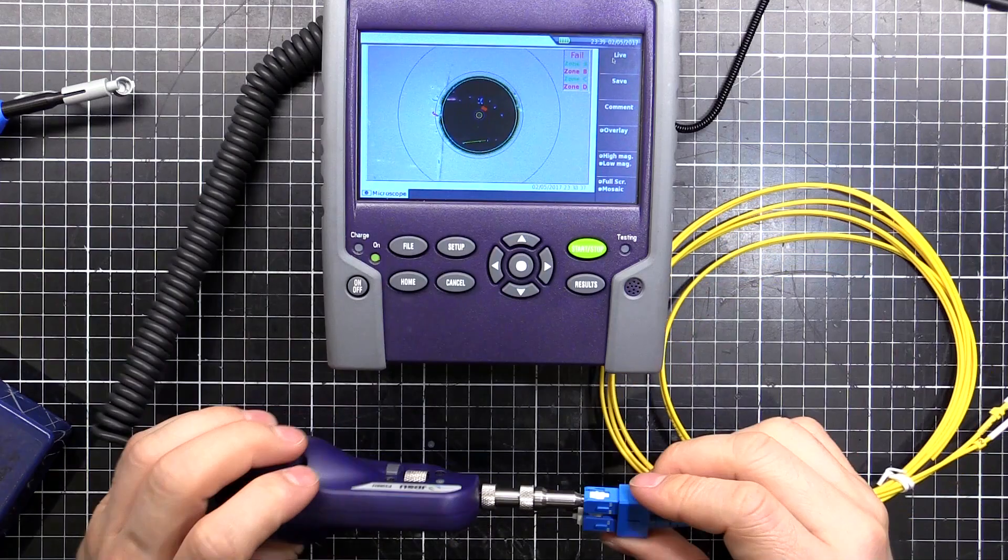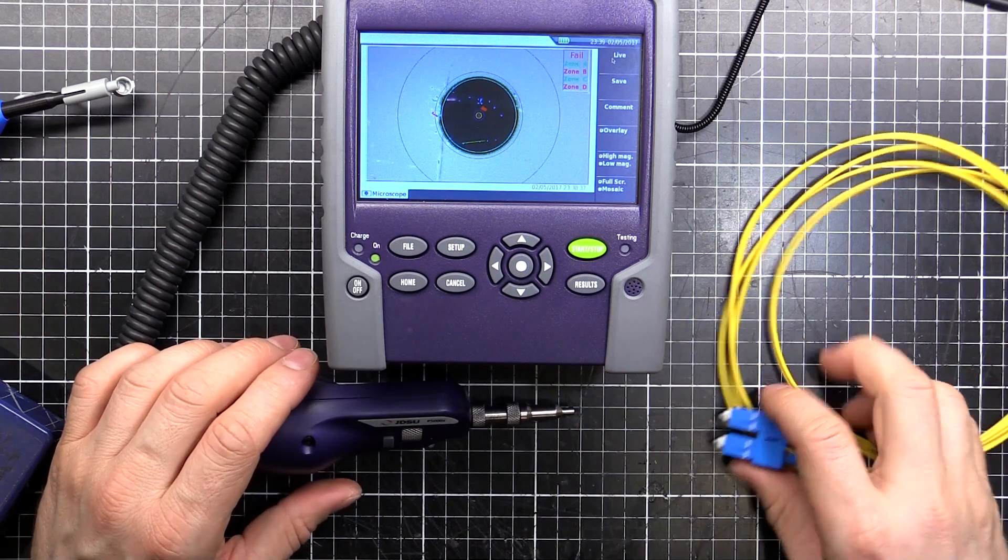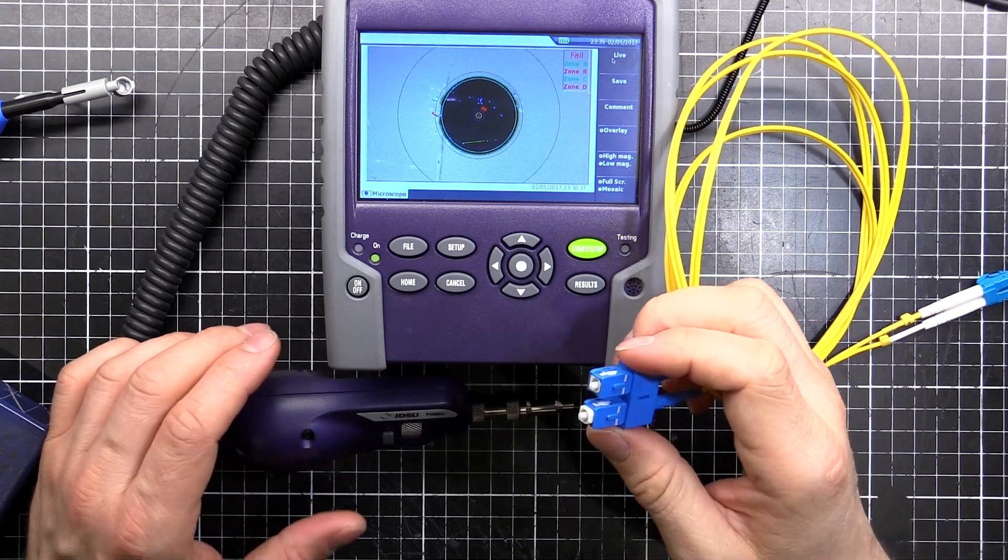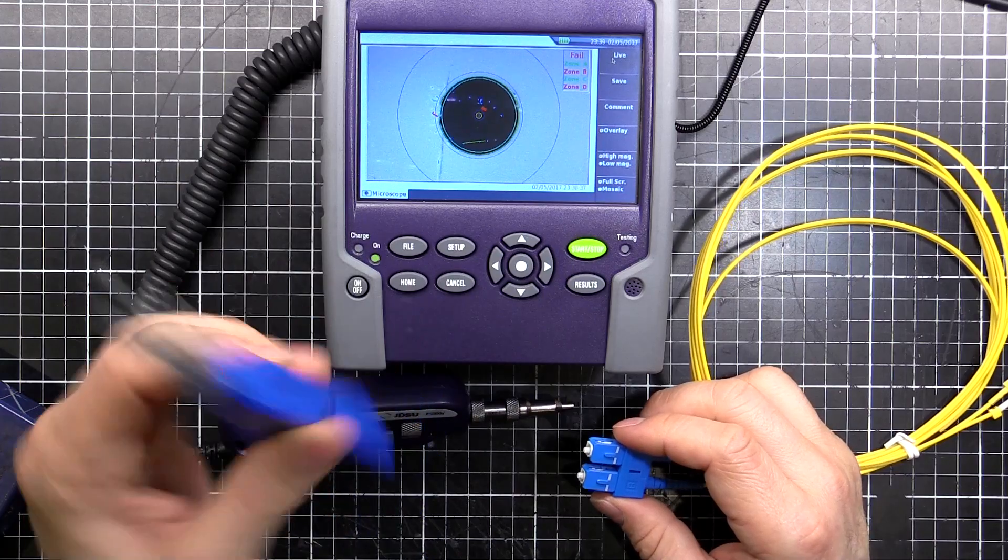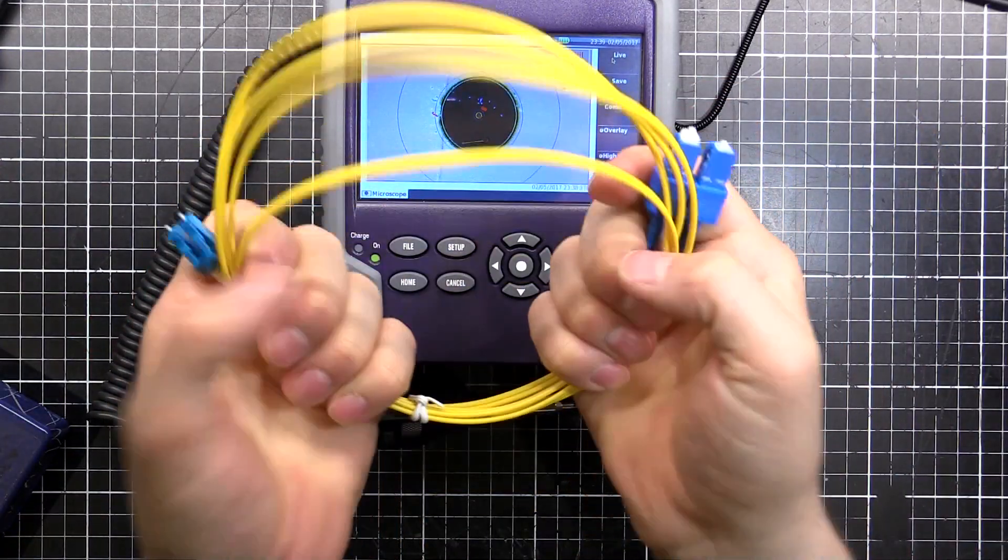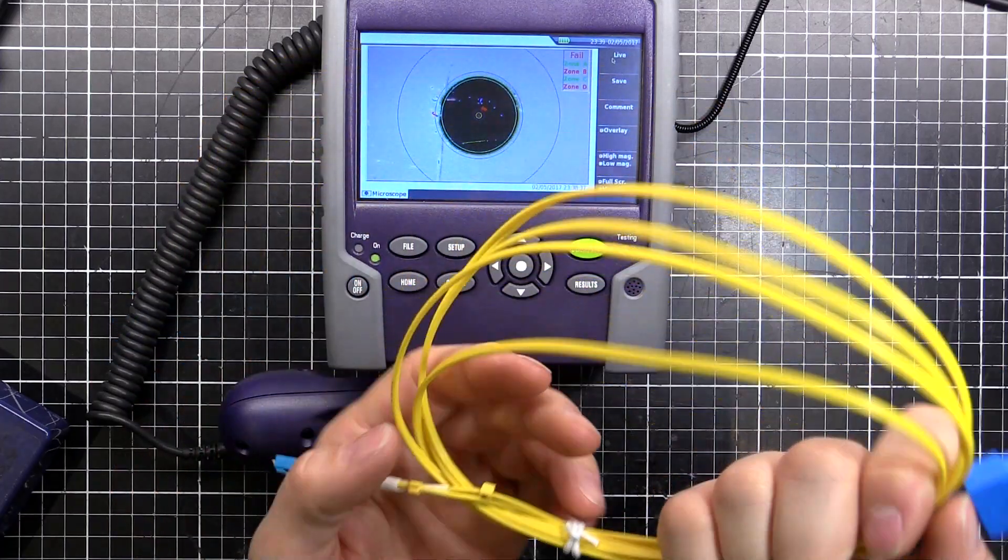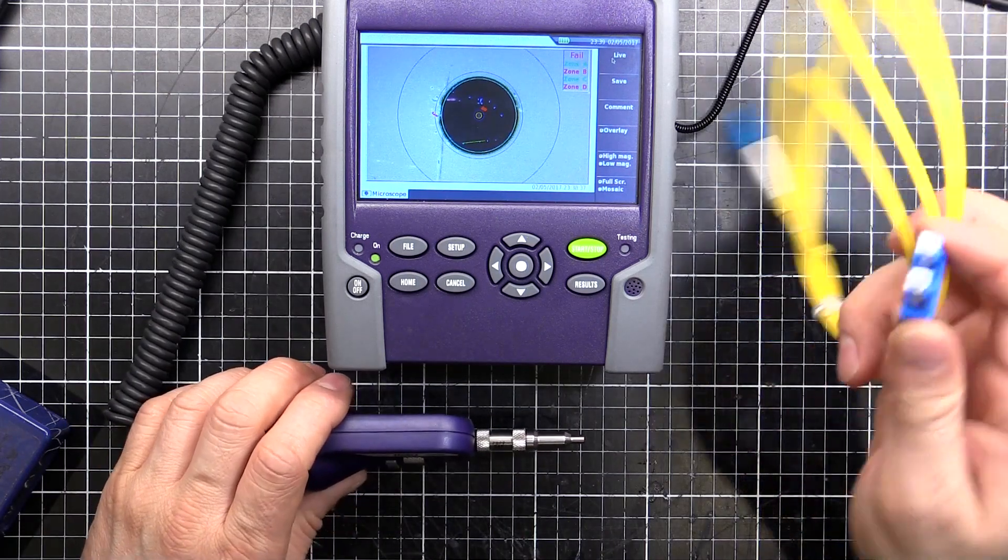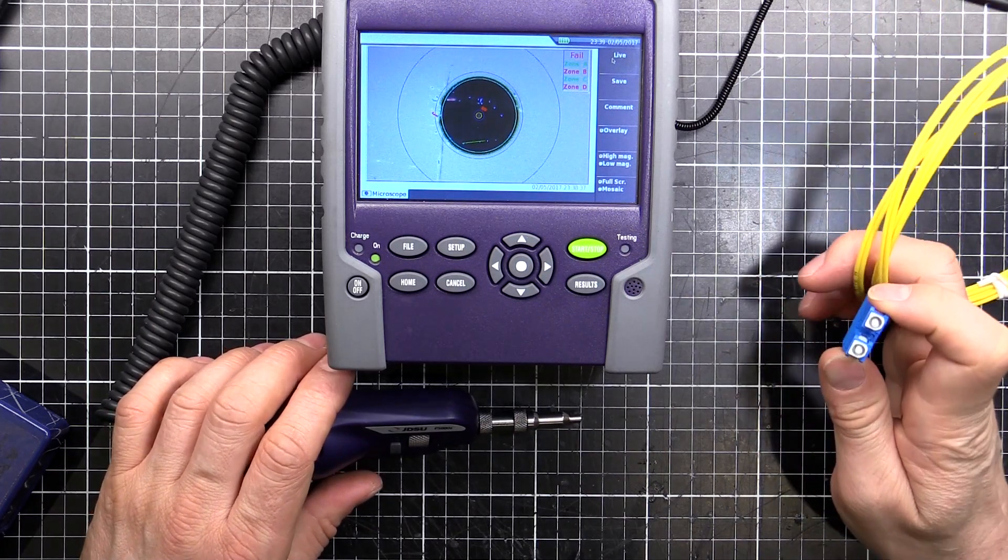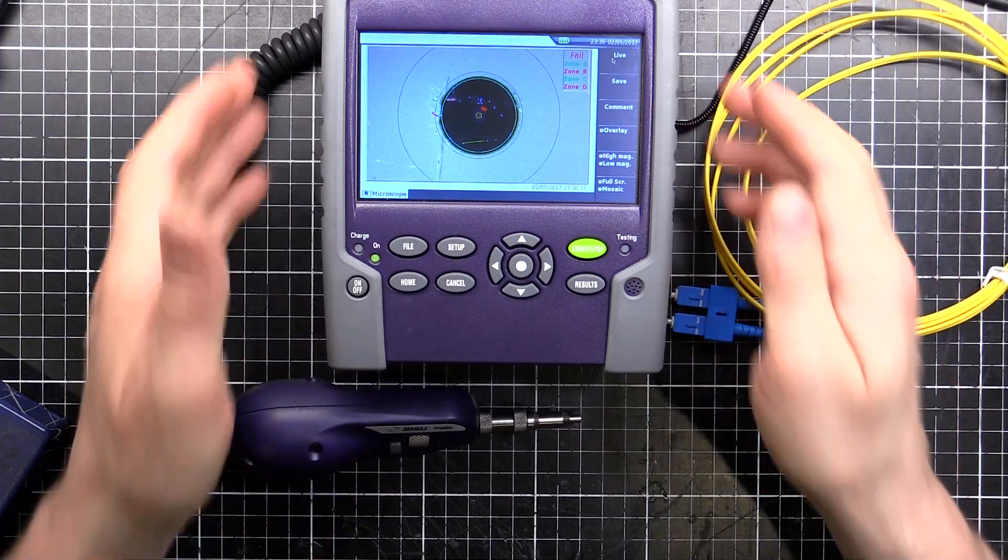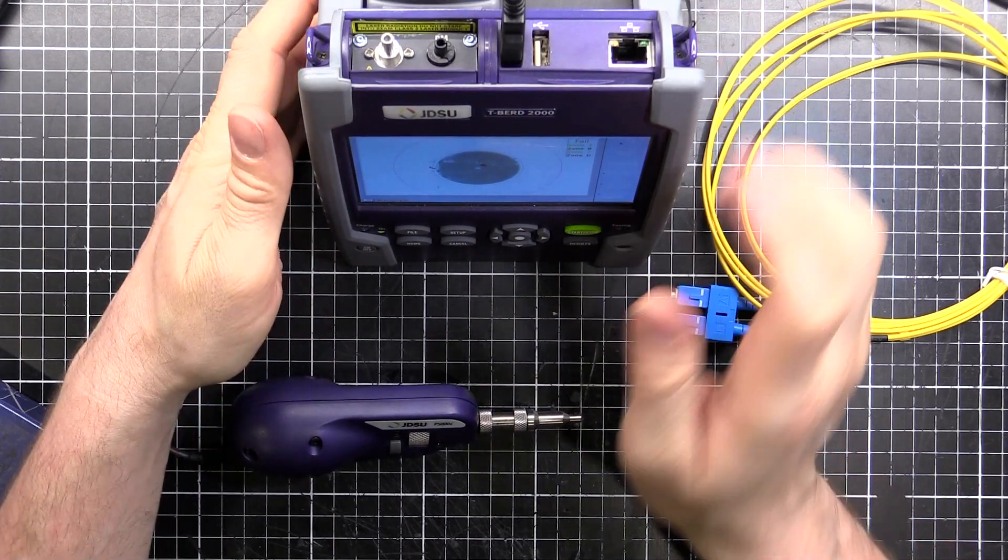So the moral of the story is keep your fibres clean and keep them protected. Just wiping on a bit of rag or a bit of paper towel or a bit of fabric isn't going to cut it. You definitely need to get a proper cleaner, and these things are cheap anyway. And also don't trust these things straight out of the pack. If it's a non-critical application, yeah, it might be okay. But if you can get a tester, definitely get a tester because you'll be amazed at how dirty these things can be. This one was actually a very clean one. Some of them look like they're being dragged through the mud and licked by a dog and all sorts of stuff.